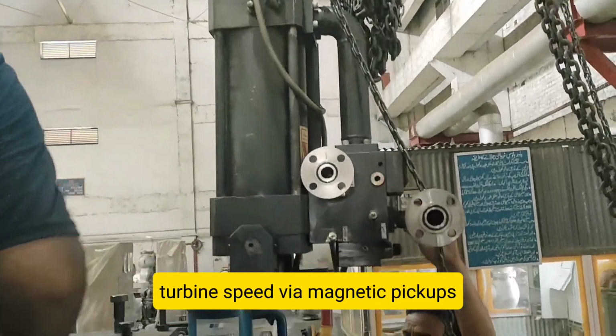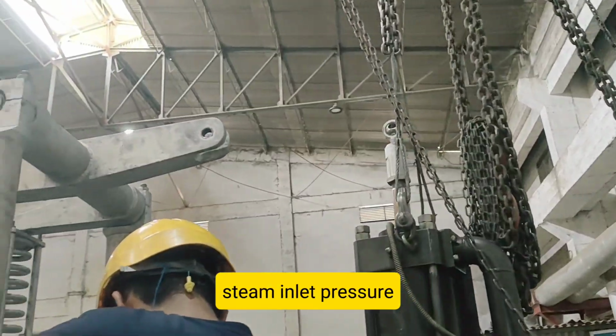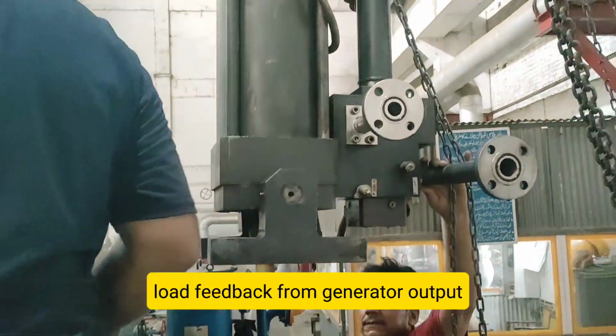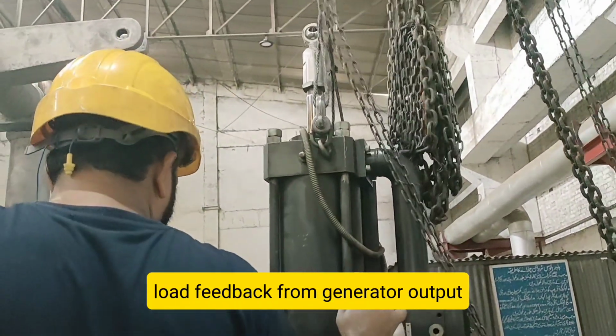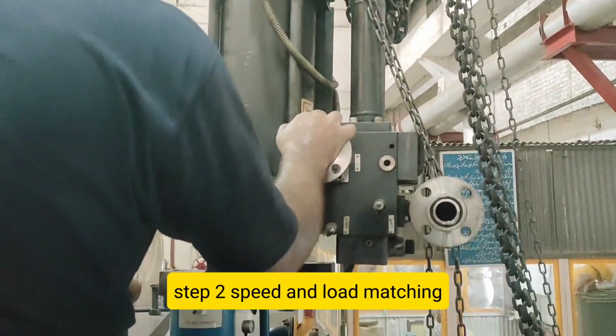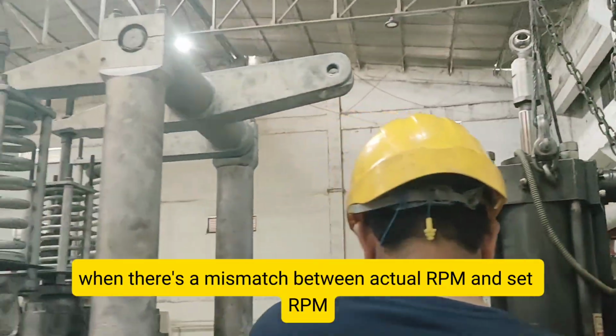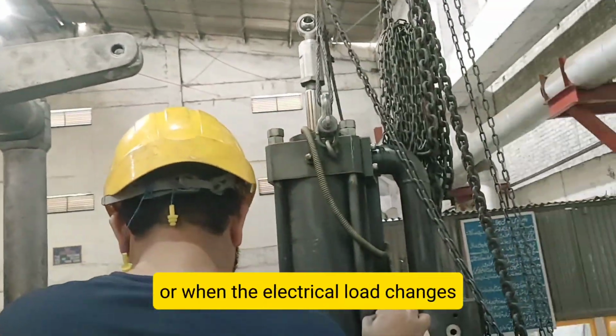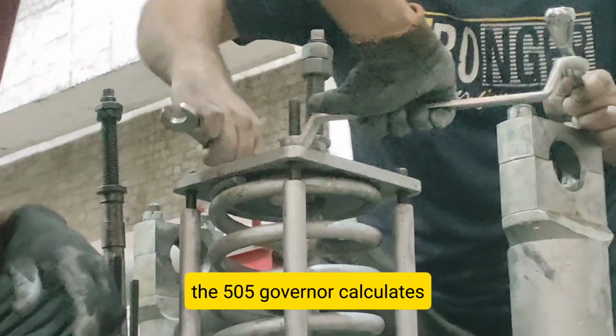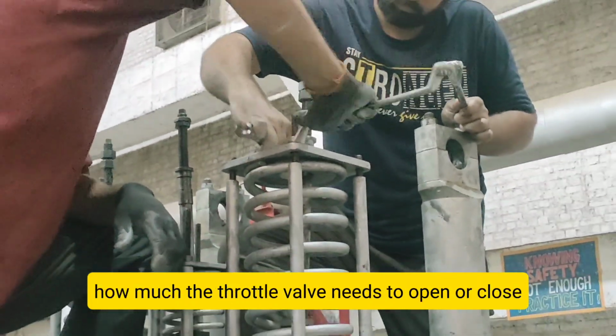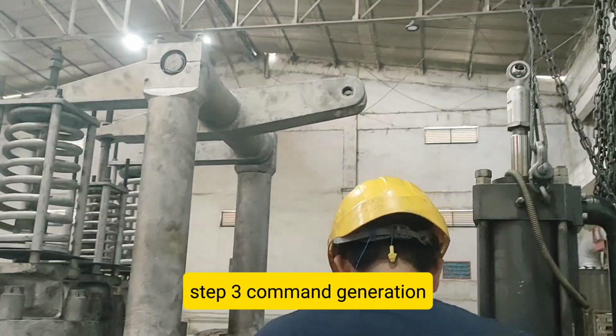How the 505 Governor sends commands to the actuator, step by step. Step 1. Sensing parameters. The 505 Governor continuously receives turbine speed via magnetic pickups, steam inlet pressure, throttle valve position, and load feedback from generator output.